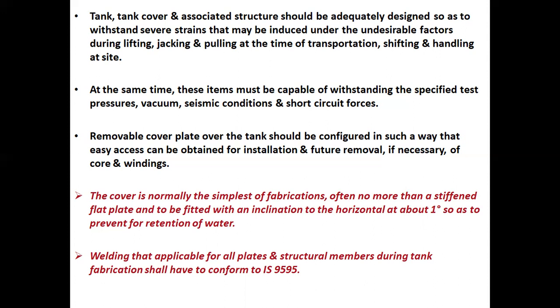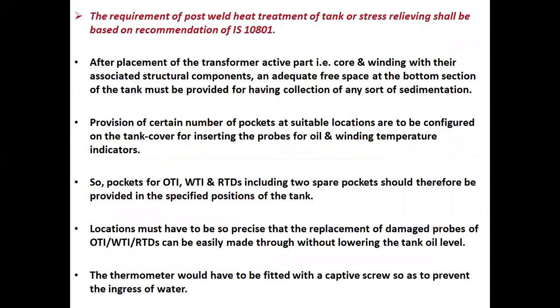Welding applicable for plates and structural members during tank fabrication shall conform to IS 9595. The requirement of post-weld heat treatment of the tank and stress relieving shall be based on the recommendation of IS 10801. After placement of the transformer active part, that is core and winding, with their associated structural components, adequate free space at the bottom section of the tank must be provided for the collection of any sort of sedimentation.